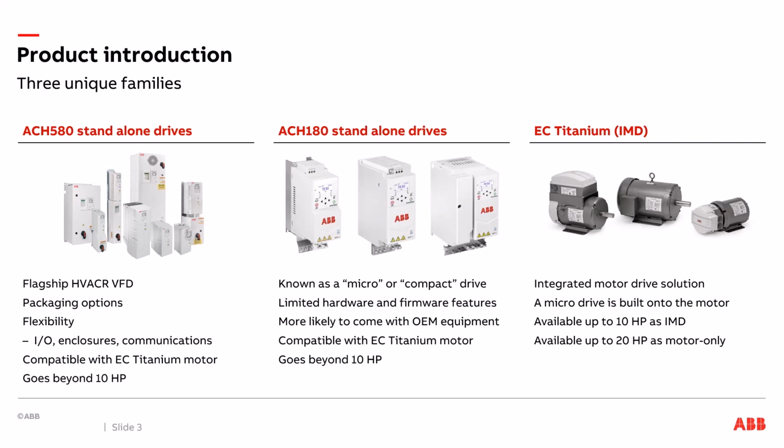First off, I should mention EC Titanium is a new cutting-edge motor technology. It's a ferrite-assisted synchronous reluctance motor. It's better than IE5 efficient. Basically, it's IE6 efficiency, except the IE6 efficiency standard doesn't even exist yet. So this is more efficient than the most efficient standard that's out there.